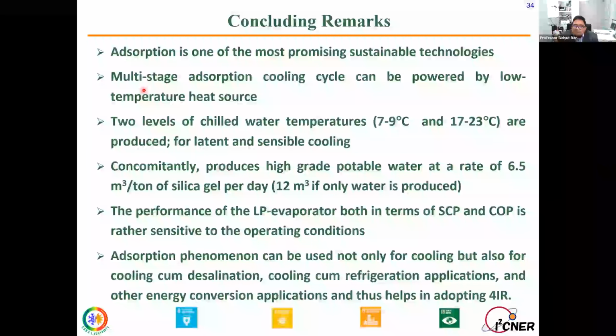So I can say that adsorption is one of the most promising and sustainable technologies, and a multi-stage adsorption cooling cycle can be powered by a low temperature heat source. Two levels of chilled water temperature, from 7 to 9 degrees centigrade and 17 to 23 degrees centigrade, are produced for latent and sensible cooling. Concomitantly, it produces high-grade potable water, 6.5 meter cube of water per ton of silica gel per day, or you can improve it to 12 meter cube of water if only water is produced in the same cycle.